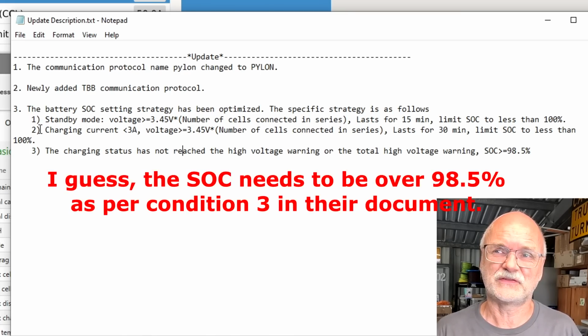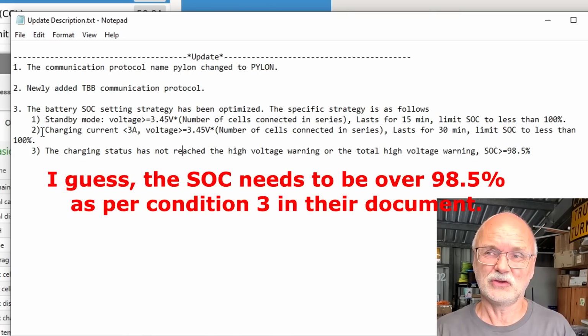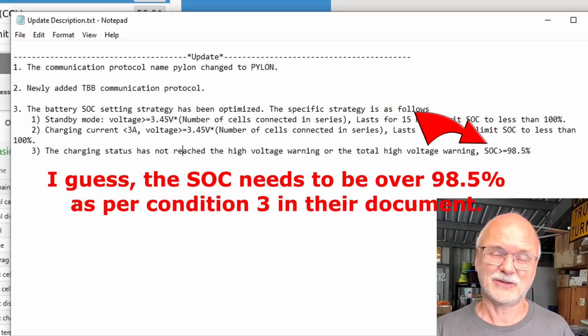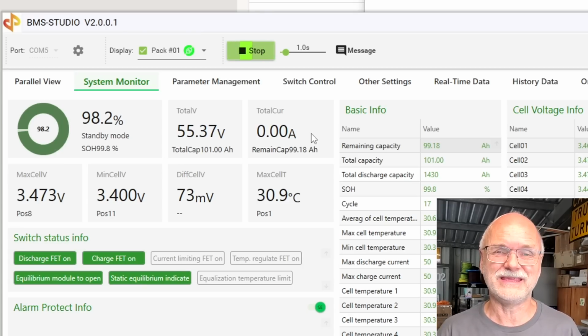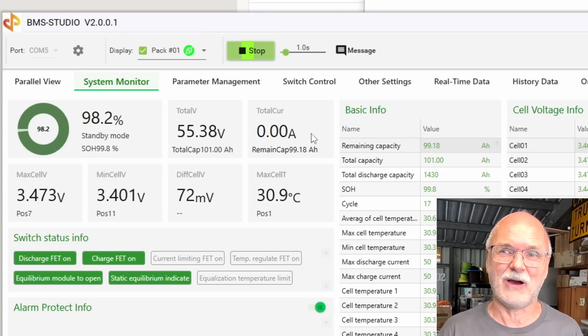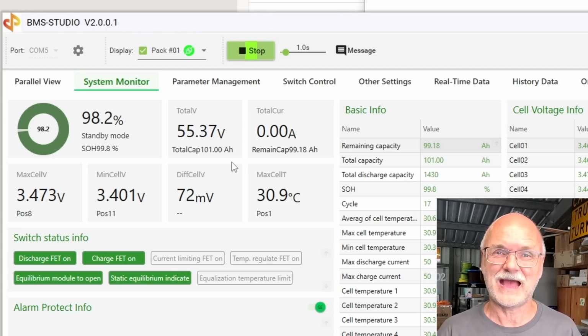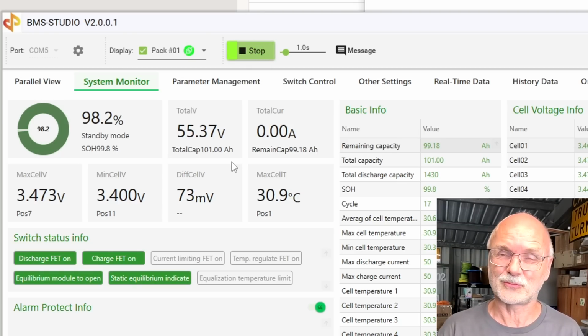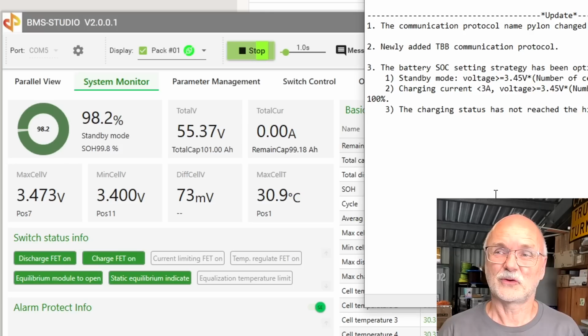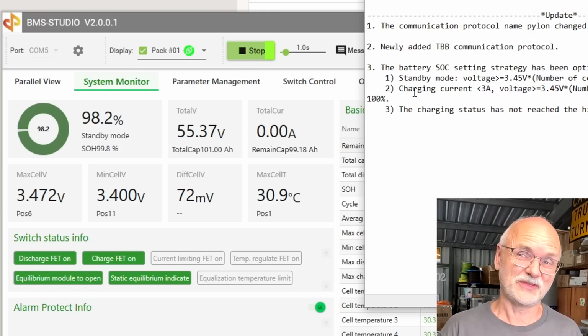Both of these conditions here are not working. I've shown you condition 2, and we cannot satisfy this either because the current cannot be under 3 amps for half an hour - the battery is already fully absorbed at 55.5 volts. It does not sustain 3 amps for half an hour. So neither of these two conditions actually trigger the 100% state of charge, and nothing has changed from the old software version 1.3.